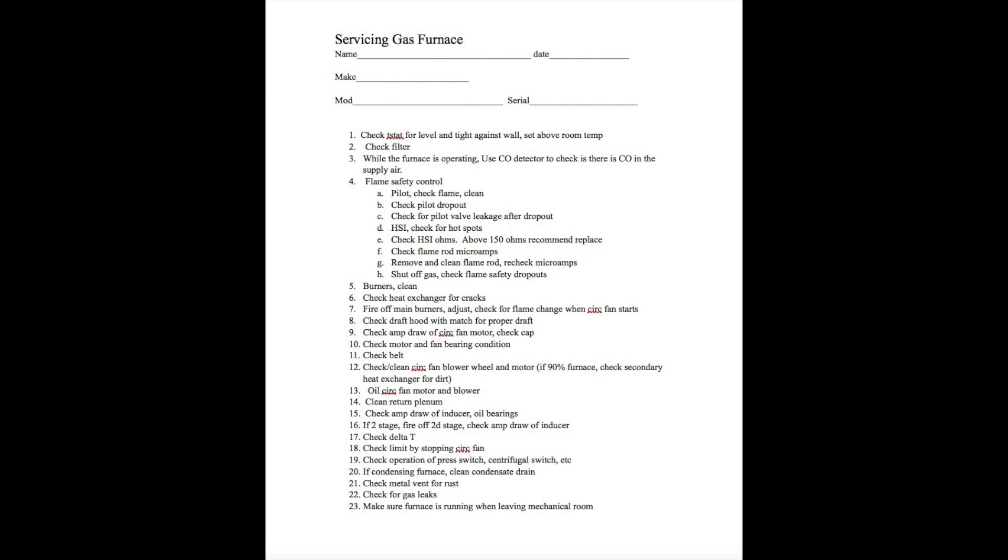If it's got a metal vent, that would be an 80% furnace. Check it for rust. Hit it with a screwdriver. Take a screwdriver tip and pretty aggressively hit especially the bottom of the pipe. If you punch through it, obviously it's got a problem.